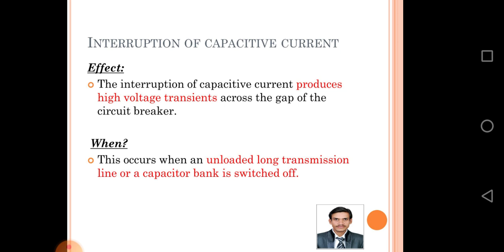Interruption of capacitive current: the effect of interrupting capacitive current produces high voltage transients across the gap of the circuit breaker. This occurs when an unloaded long transmission line or a capacitor bank is switched off.